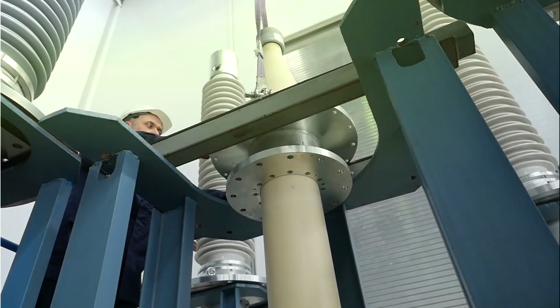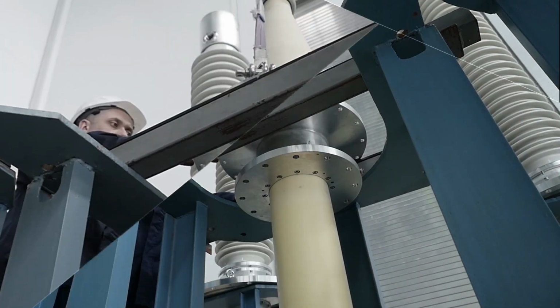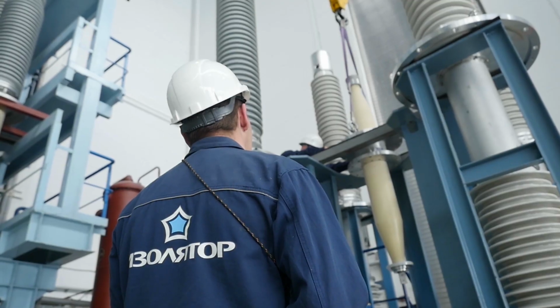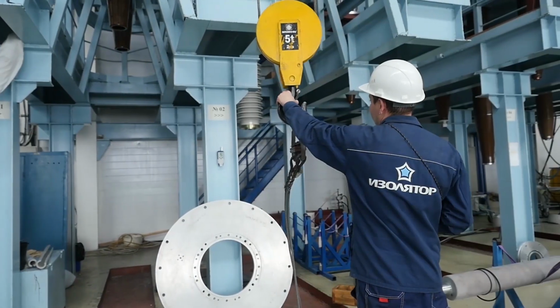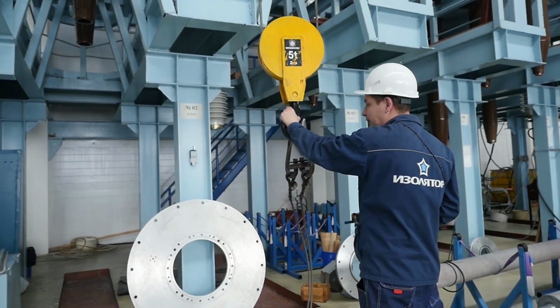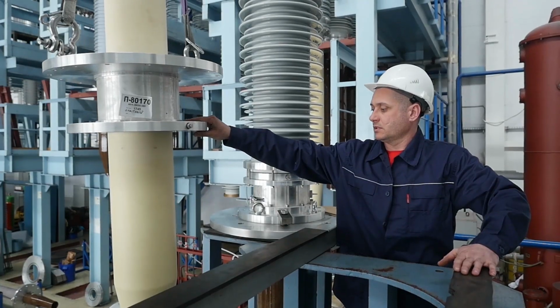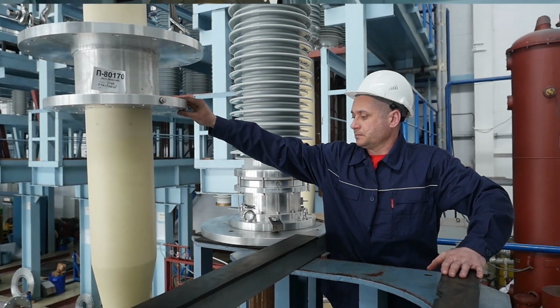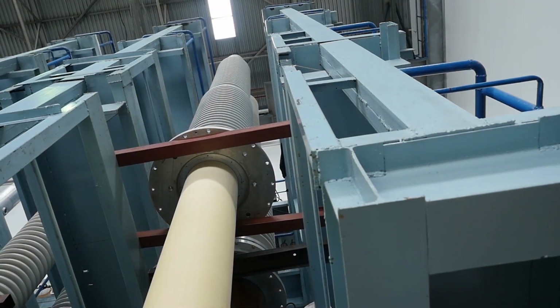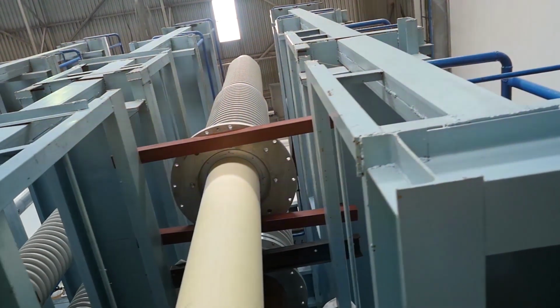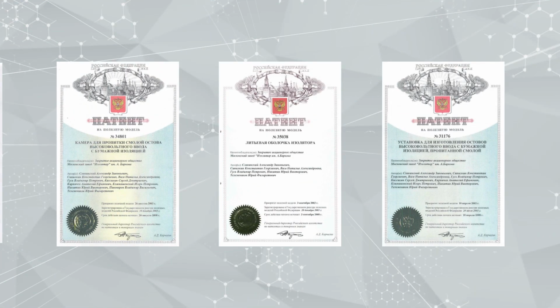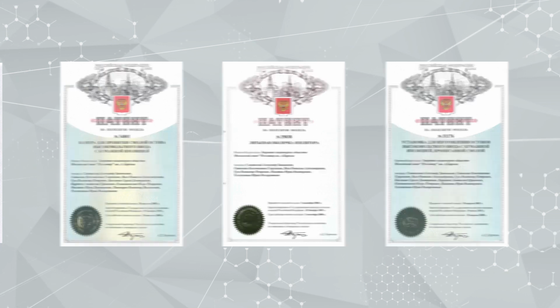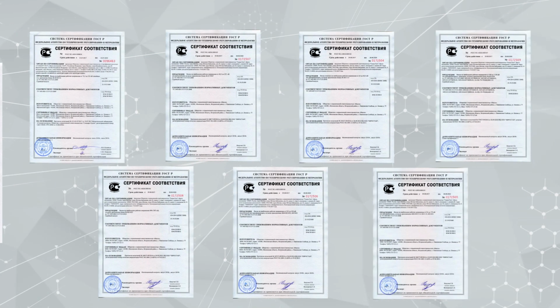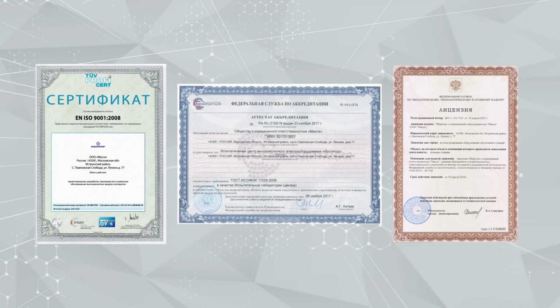The main difference of those types of insulation from RIP insulation is that a special non-woven fabric or scrim is used at winding instead of paper. Due to the fact that there is no cellulose in the insulation structure, both types of insulation are not able to be moistened during transportation and long-term storage, which allows storage of bushings in any conditions without the use of special sealed cases. The proprietary technologies are protected with 12 international patents, including patents on the making of RIP and RIN insulation and production of the external polymer insulation for voltages from 35 to 330 kilovolts.